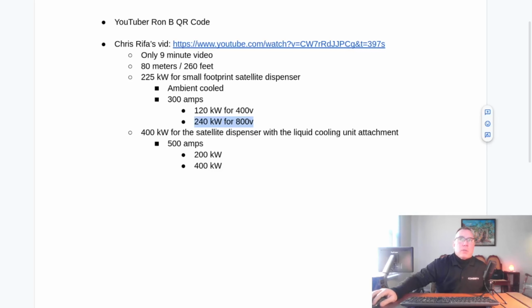The satellites with the liquid cooling attachment can dispense at 500 amps. So at 400 volts, that's 200 kilowatts. And at 800 volts, that's 400 kilowatts.